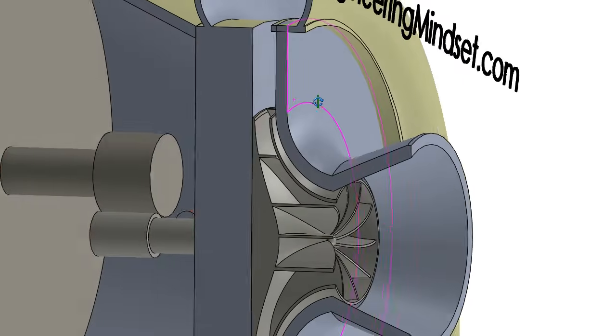Now the purpose of the diffuser is to simply slow the refrigerant down, and as it does so, it converts all the refrigerant's kinetic energy into static pressure. And this increase in pressure is known as the lift, and that's also known as the head pressure. Now lift and head pressure, and static pressure in there, all it is, is just the difference between the pressure of the refrigerant in the condenser and the pressure of the refrigerant in the evaporator. That's literally it.